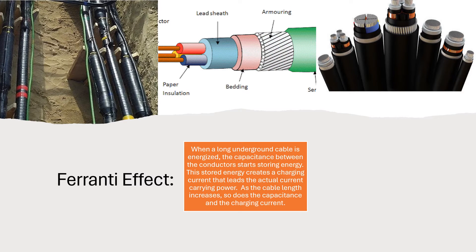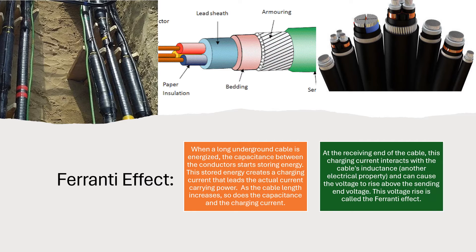Ferranti effect. When a long underground cable is energized, the capacitance between the conductors starts storing energy. This stored energy creates a charging current that leads the actual current carrying power. As the cable length increases, so does the capacitance and the charging current. At the receiving end of the cable, this charging current interacts with the cable's inductance and can cause the voltage to rise above the sending end voltage. This voltage rise is called the Ferranti effect.